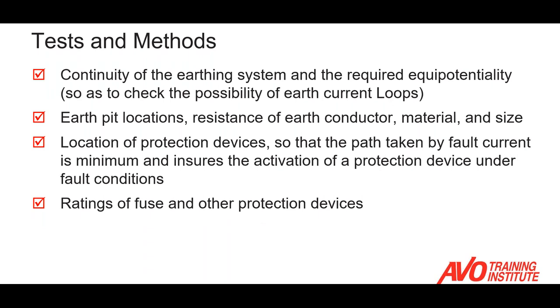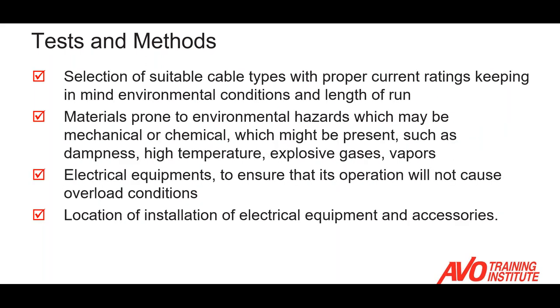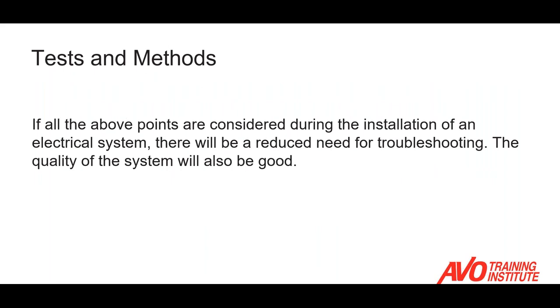We also want to keep in mind the location of the protection devices — where are they, and what are their ratings? Also consider the selection of cable type due to the environmental conditions it will be placed in, and make sure electrical equipment is rated for the environment it will be exposed to, as well as installed per the manufacturer's specifications. All of these checks should ideally be performed during the installation phase to reduce the need for additional troubleshooting and to verify the integrity of the system before putting it in service.